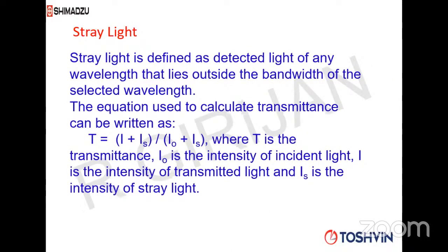Stray light, you must have heard about stray light. Even USP also has got stray light specifications. Now, you are all pharmaceutical people, if you look at method number 857, that is the latest USP method 857, it is the validation of UV visible spectrophotometer. It's a long chapter and a little complex to understand, and there are so many parameters given in that.